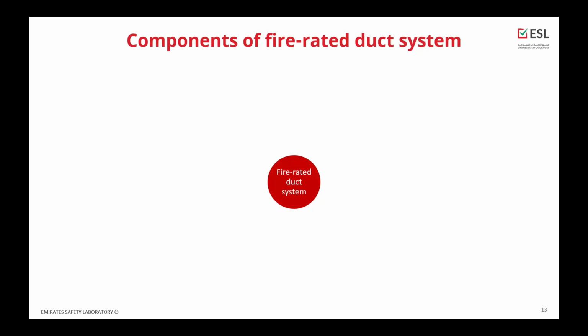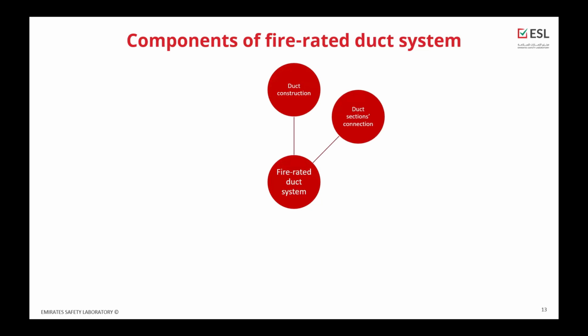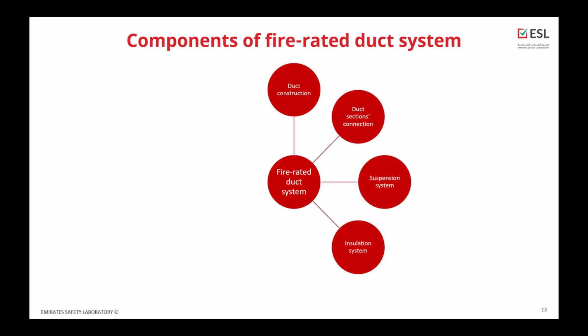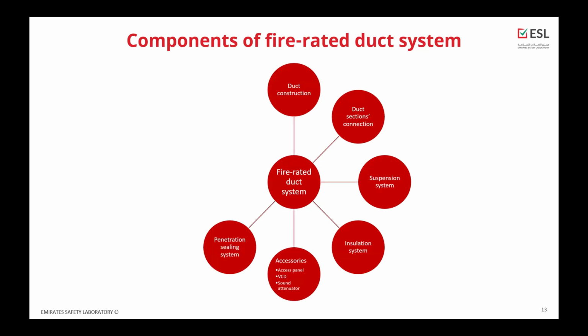As I said, we are talking about duct systems. So what are the components of such a duct system? It's obviously the duct construction itself, right? How the duct is installed. What the joints between the duct sections are and how they are sealed, what the other related factors are, the suspension system and devices. The insulation system for insulating the duct. All accessories within the duct system, compensator, access panel, etc. The penetration sealing system. This is very important to understand: penetration seal system belongs to the duct system itself. Installation, how the duct is or should be installed, instruction manuals, method statement if applicable. And application, which means how and where this duct can be installed.